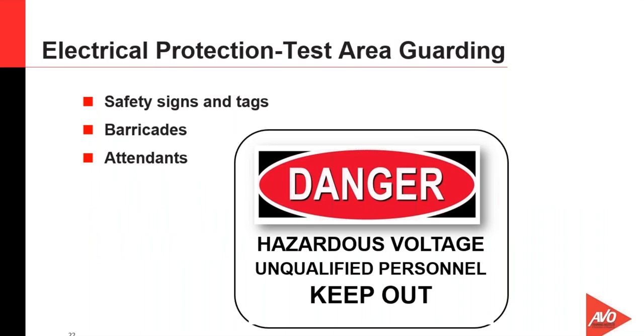Okay, after we have our test area secured, then essentially guarding becomes an issue. We have three basic OSHA requirements for test area guarding, or three methods to apply. One of them is safety signs and tags. If a safety sign or tagging system can work as far as protecting the area, then that would be adequate. Most of the time, these are used in conjunction with each other. You'll have multiple issues being used. We'll have safety signs and then possibly barricades, and could have an attendant as well.